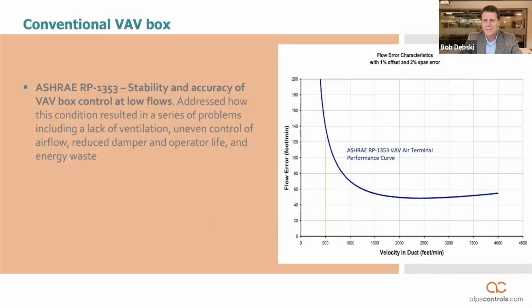If you look at this curve to the right of your screen, you'll see duct velocity on the horizontal axis, and on the vertical axis, the error in flow measurement of the VAV sensor. If you look closely, below about 1,500 feet per minute, you start to lose accuracy of the traditional airflow measurement. By 500 feet per minute, you've lost almost complete accuracy, and it becomes very inaccurate. This has been determined to be a cause of most of those problems that we showed earlier, including hunting in control or poor control, and premature wear out of damper actuators. These are all things that can be attributed to the inaccurate sensing of airflow in air valves.